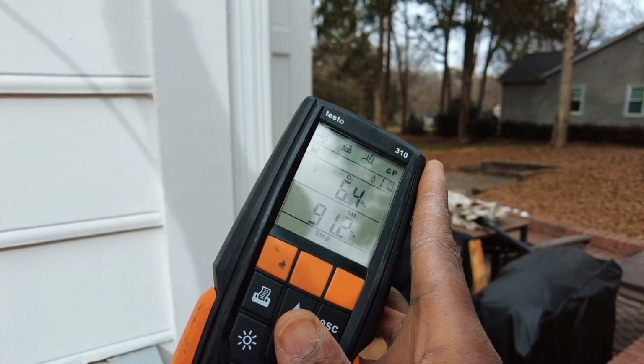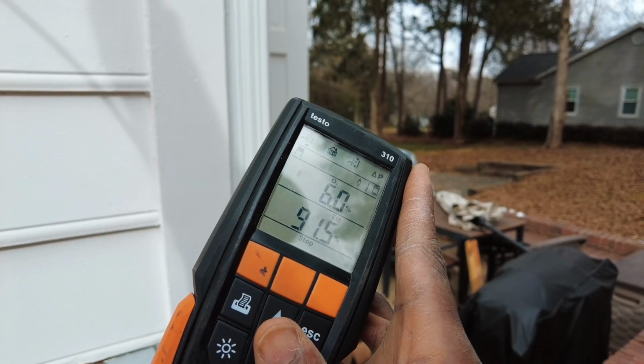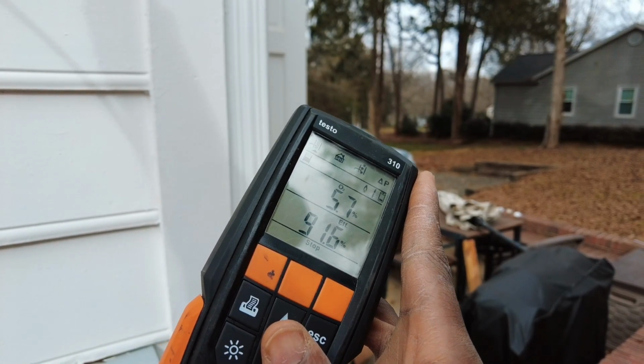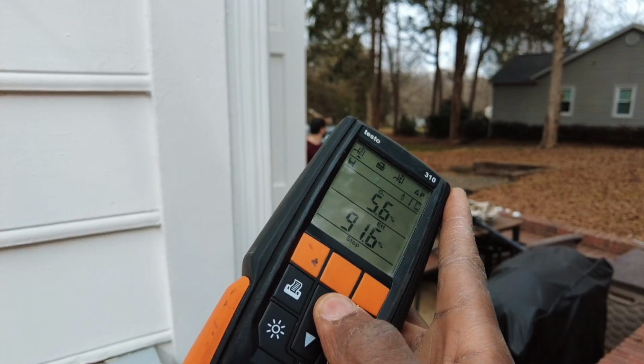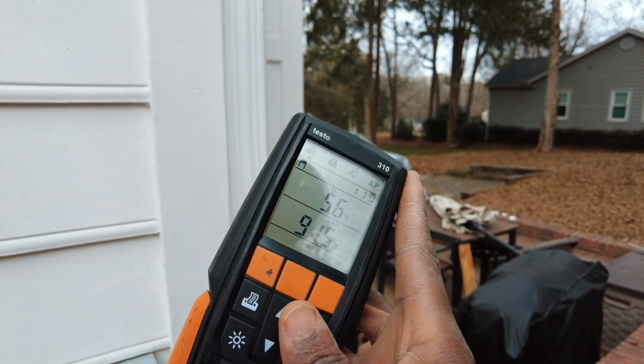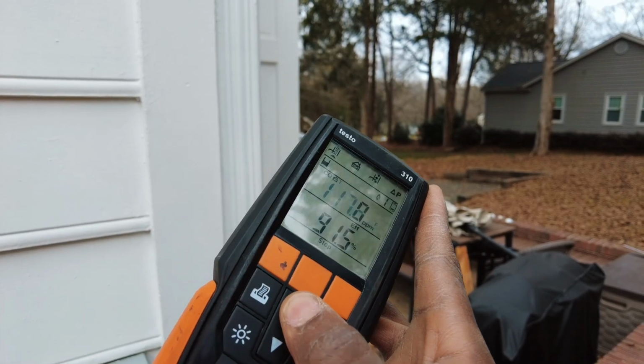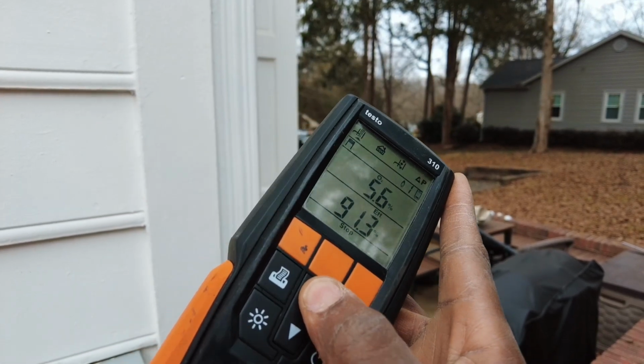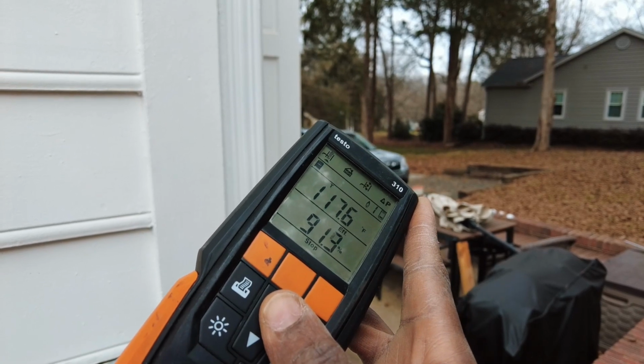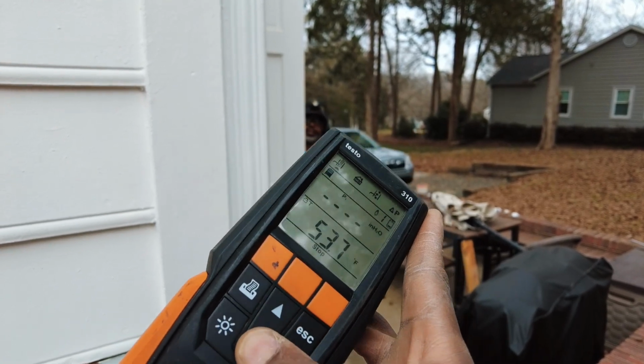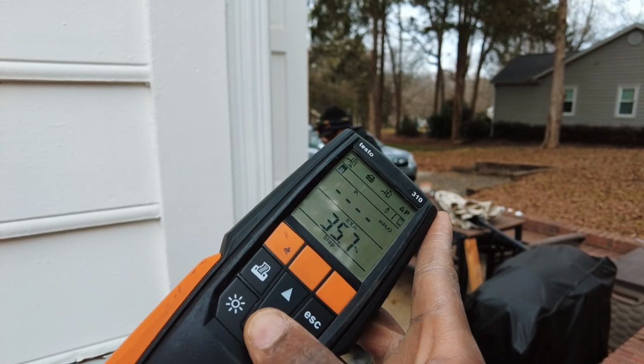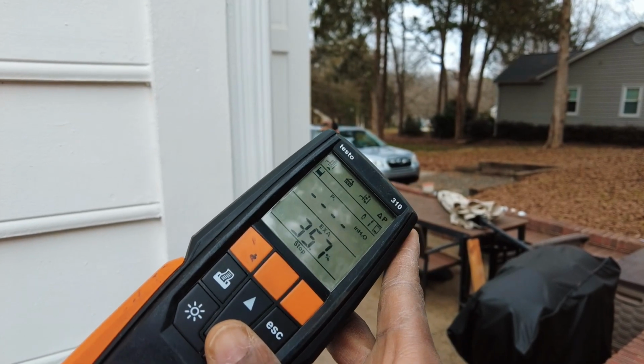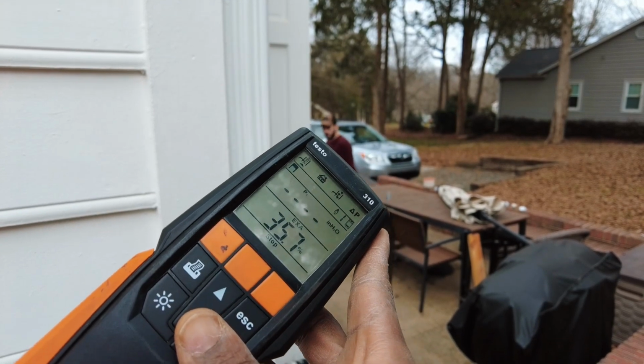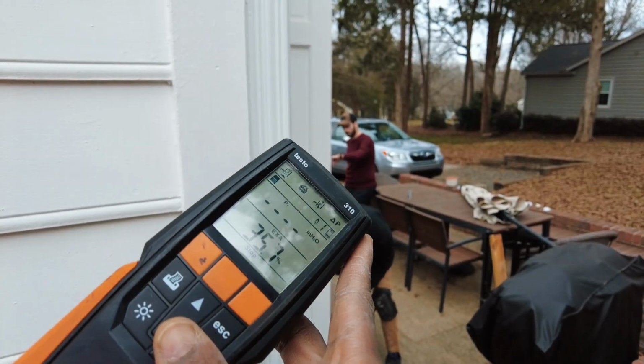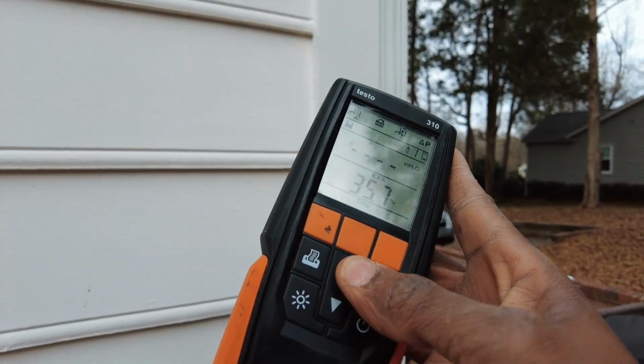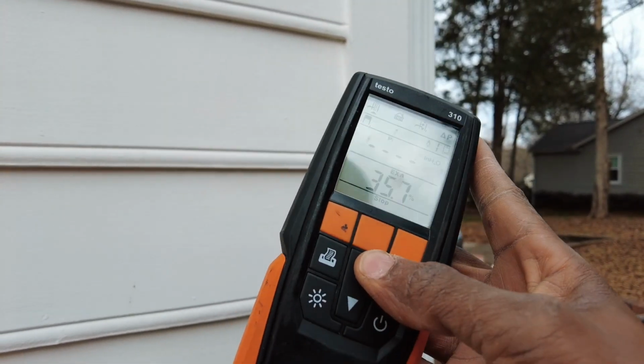Might need to turn that gas pressure down. Was it 3.6 for the gas pressure? 3.49. Damn. 6 input. Our O2 is looking kind of low. I'm going to let this run a little bit longer. Yeah, I probably would. Let's turn the manifold pressure down. Try 3.2. Just put it at 3.2. Yeah, we got 35% excess air. That's pretty low.